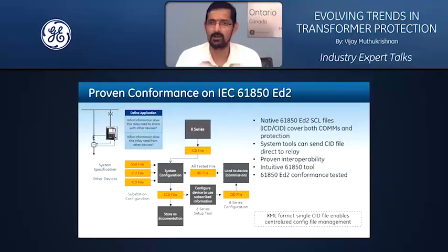One of them is you have the 61850 configurations handled by the XML formats, and then you have a proprietary way of handling the protection settings. The power of integrating them and giving you a single CID or an ICD file is that you can actually deploy that file directly to the relay without the need of the setup program or the software for that particular device itself, which allows you to centrally manage your config file deployment.